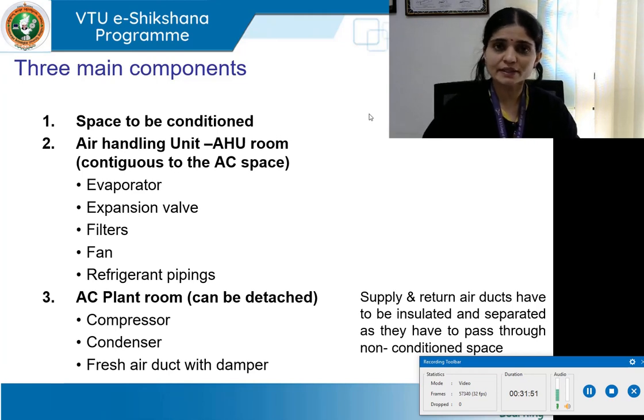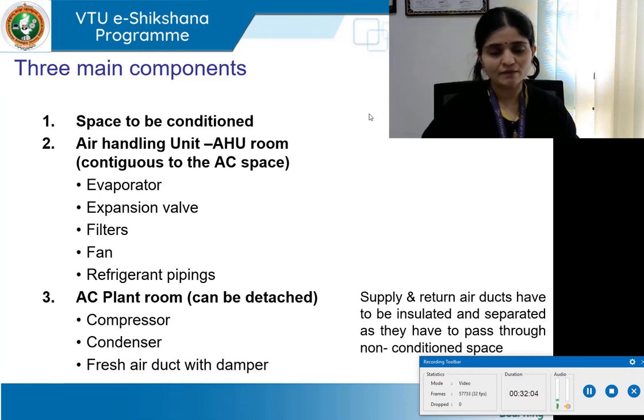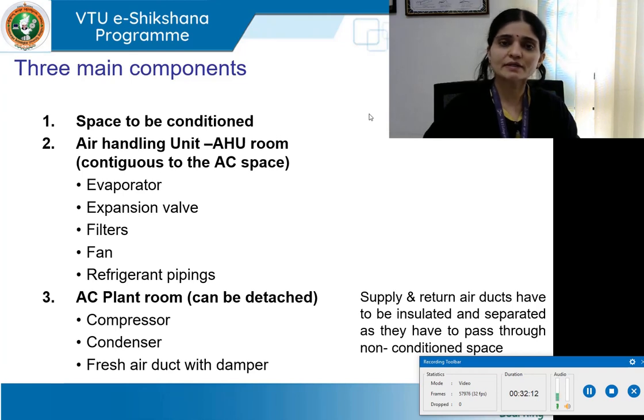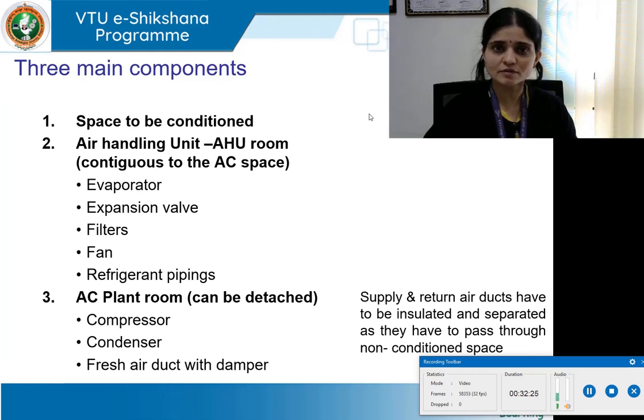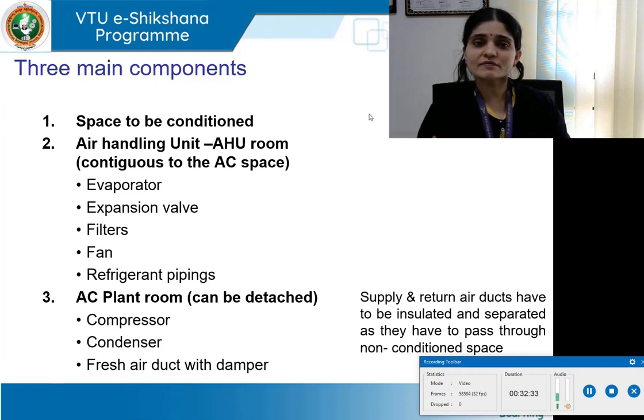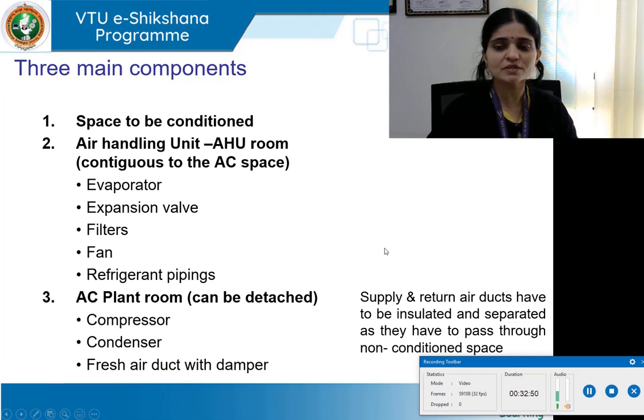The supply and return air ducts running in the plenum space must be insulated because they pass through non-conditioned space. For example, the supply air duct carries cooled air — say at 17 degrees — and if it passes through the warmer plenum space without insulation, the temperature may rise before reaching the intended space. Hence insulating these ducts is essential for better efficiency.